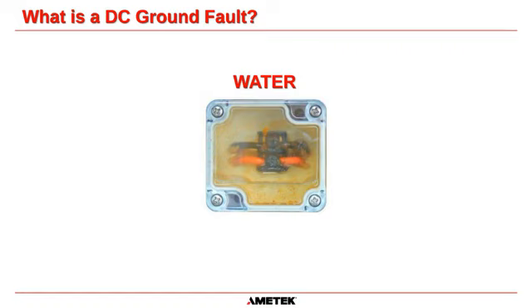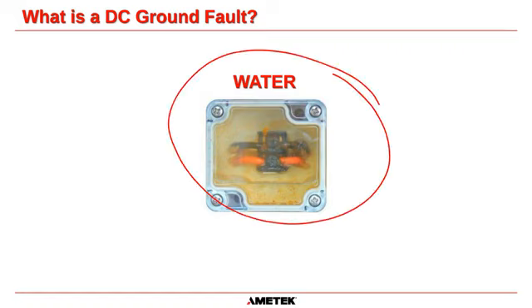This is actually a very common ground fault path in refineries and petrochemical plants, because a lot of junction boxes, analyzers and so on are mounted outside in the weather, and you tend to find that most ground faults appear magically when there's a thunderstorm and things get soaked, and that causes one of the polarities to go down to ground.